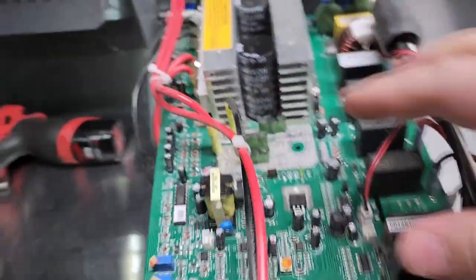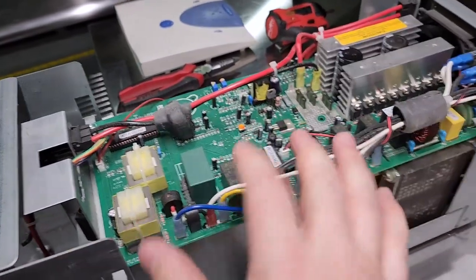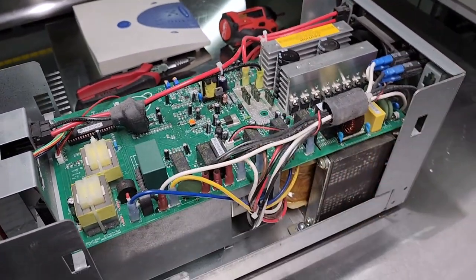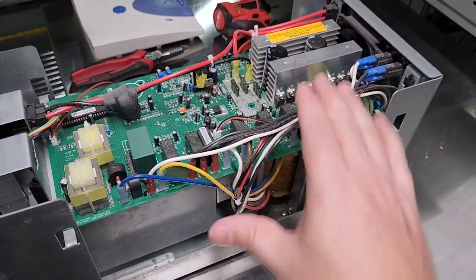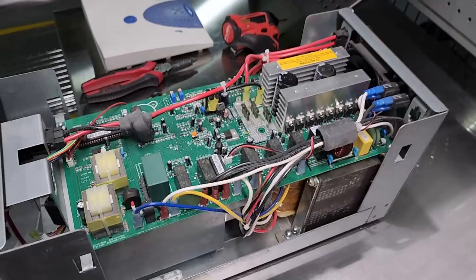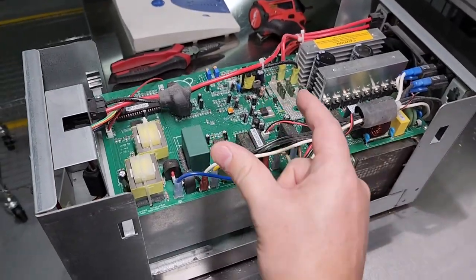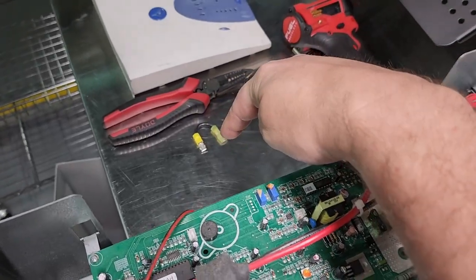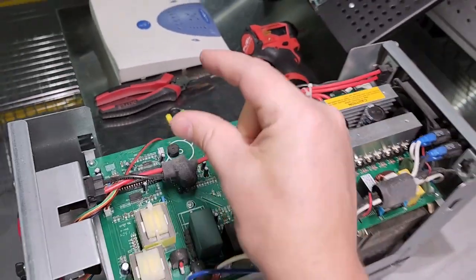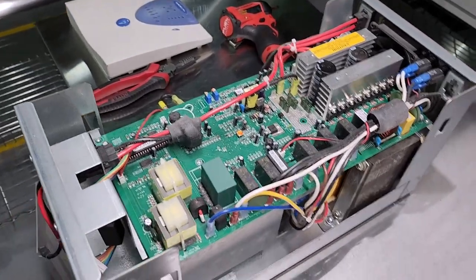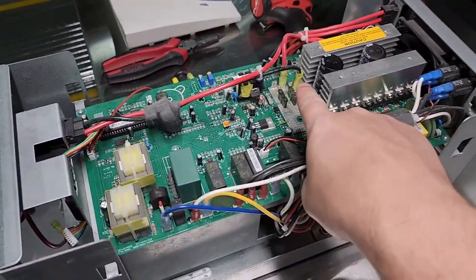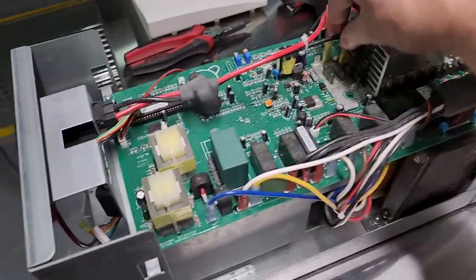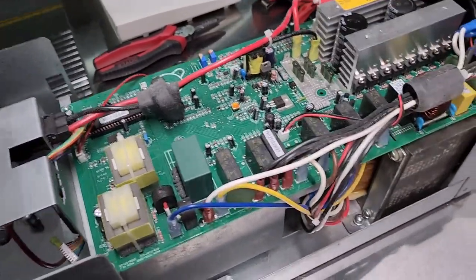When this goes back together, you have to check those because 24 volt batteries can pull a lot of amperage, especially if this guy is maxed out. It does have overload current protection, but you still want to make sure that all your connectors are really tight. Even the jumper that I took out, I'm going to crimp down on the spades a little bit. By crimping down on the spades, you're going to make sure that it fits really tight on these spade terminals.